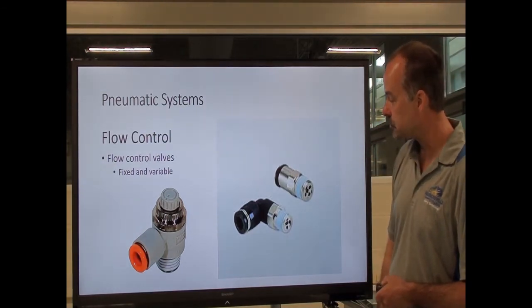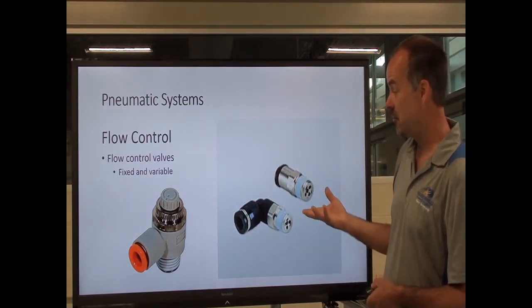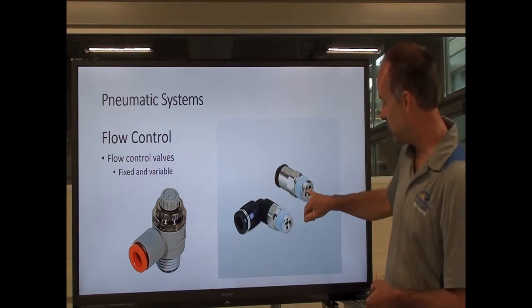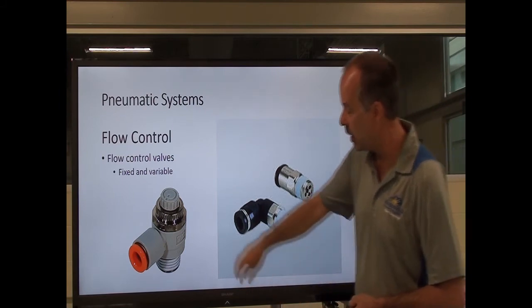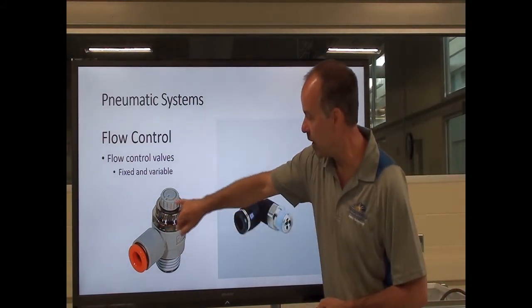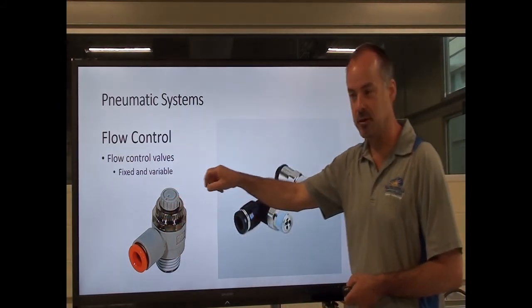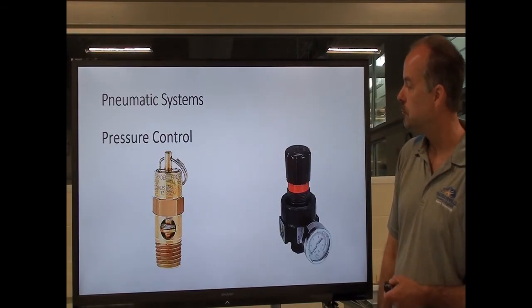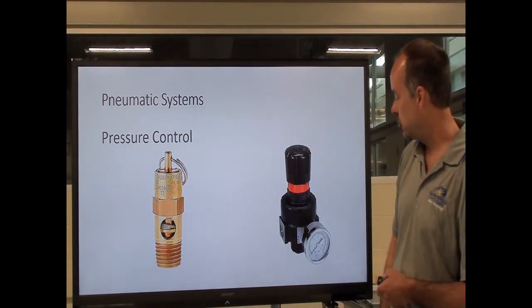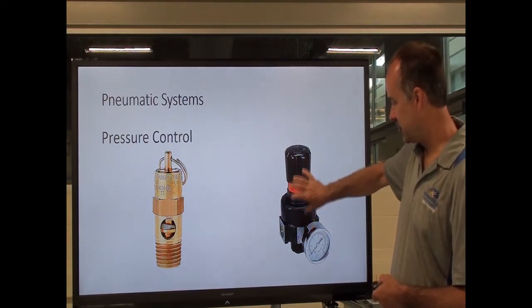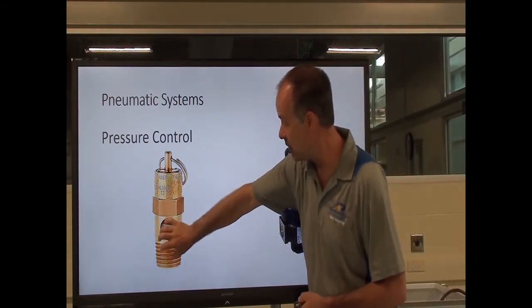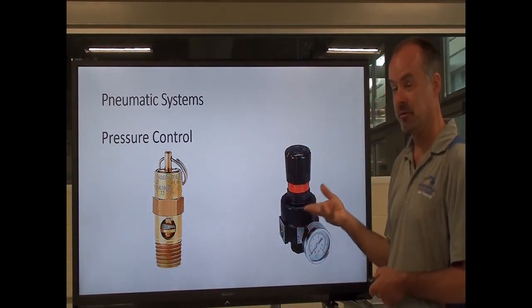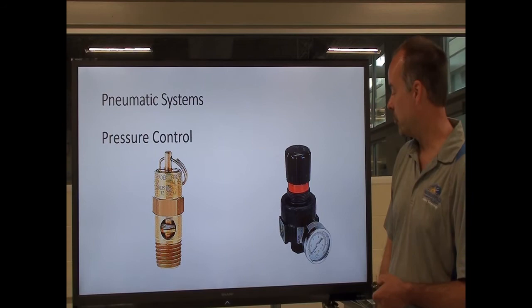Flow control valves — again, we have fixed and variable. A fixed flow control valve just has smaller orifices to restrict the flow. A variable flow control valve has an adjustment you can use to actually adjust the flow of air. Pressure control: we have adjustable regulators, and we have safety valves to protect the components in the pneumatic system from an overpressure situation.